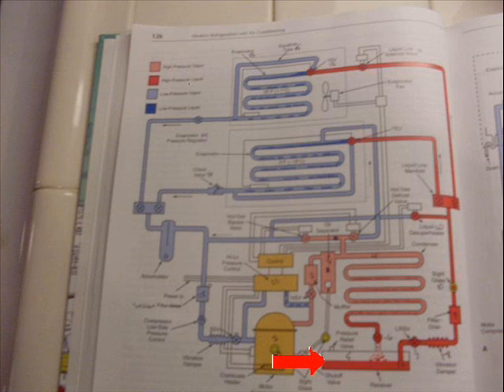On the outlet of the receiver tank, generally welded directly to it, is the liquid receiver service valve or king valve. The king valve will allow us to do three functions. Number one, it will allow you to charge on the high side with liquid with the system running if you know exactly what you're doing. If you don't, you will die.